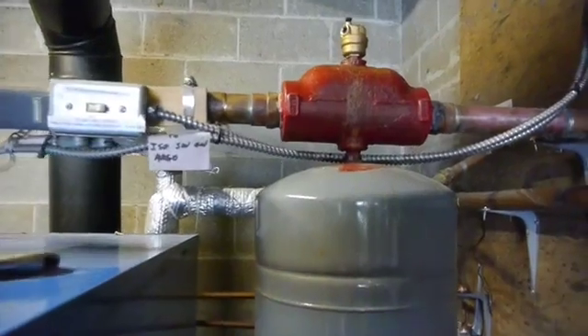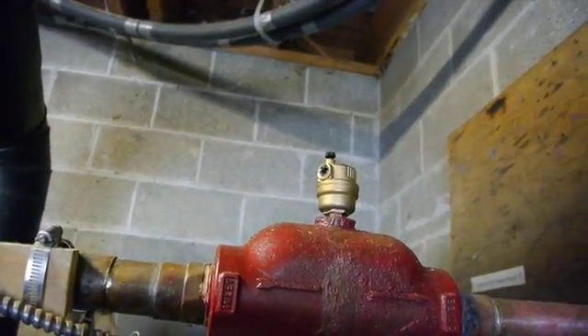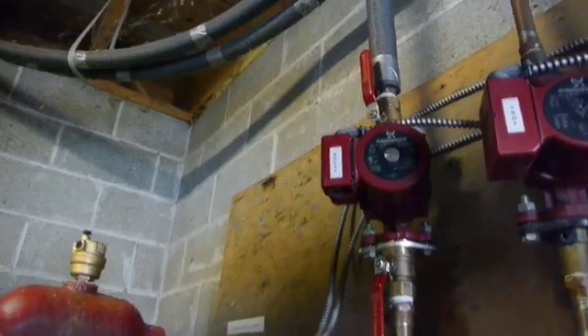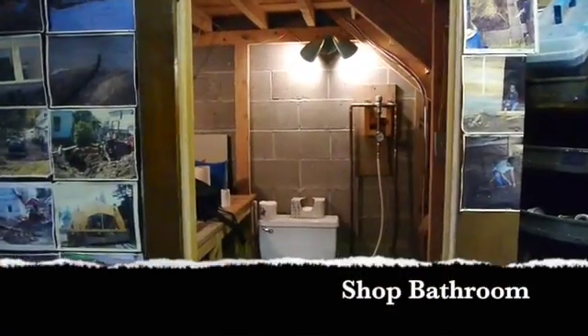So I re-engineered things and put that in new. I also had to replace the boiler drain. This air purge unit I replace every year, and this year I had some leaks in my isolation valves so I replaced those on the main pump.